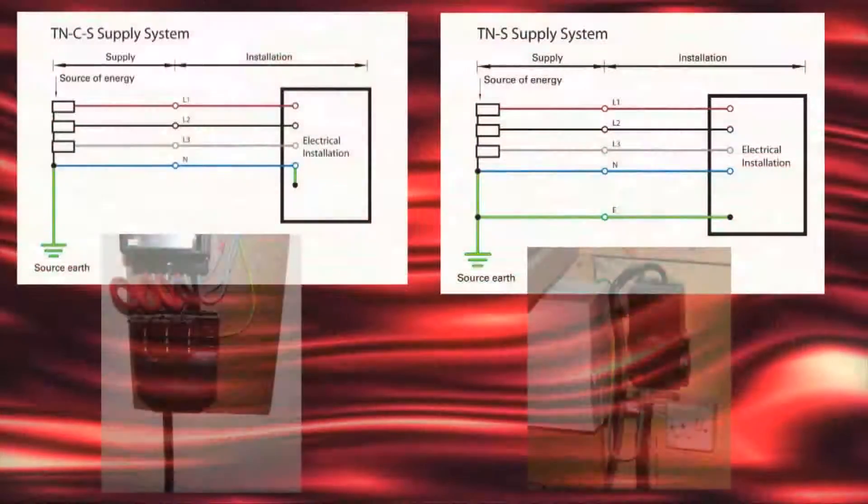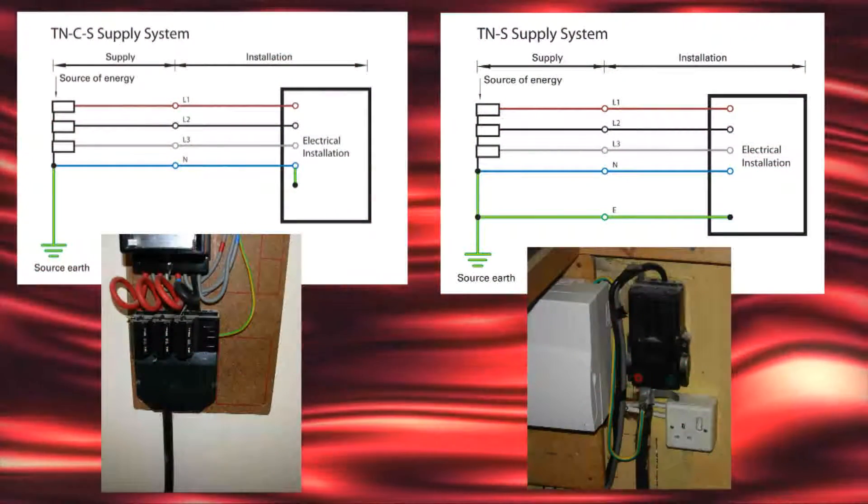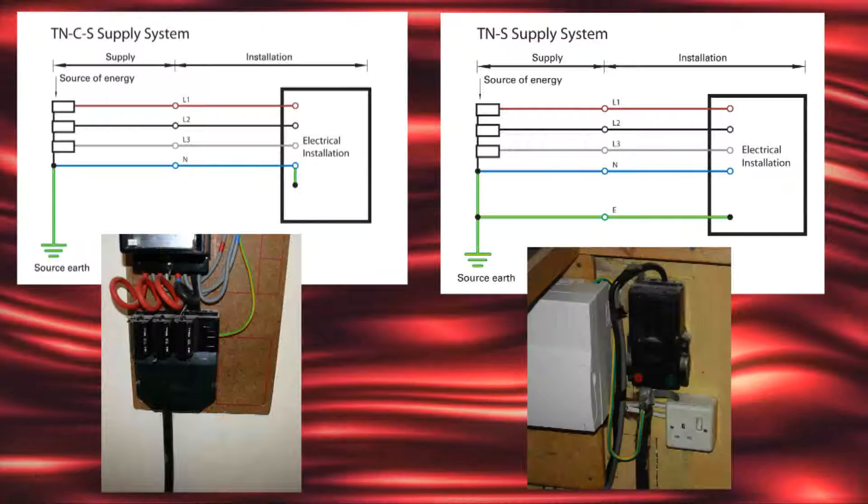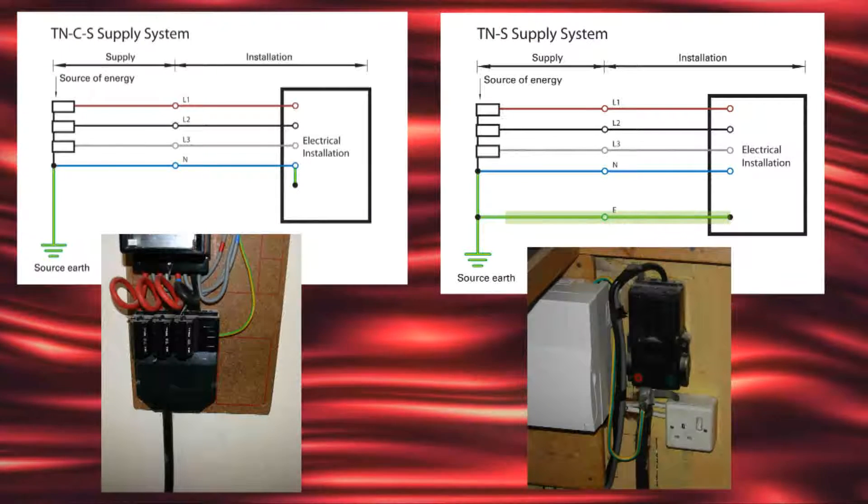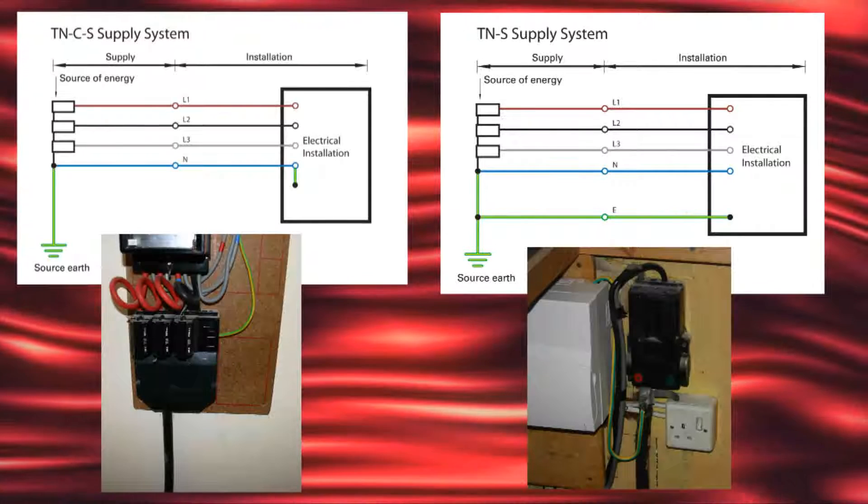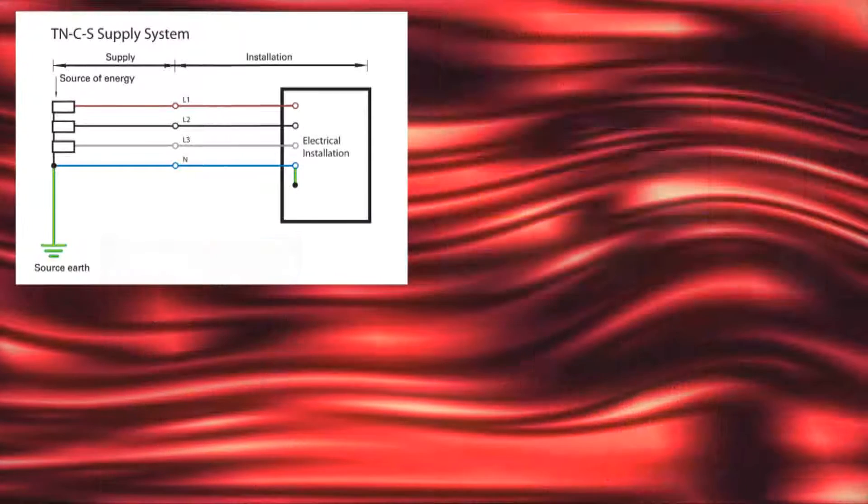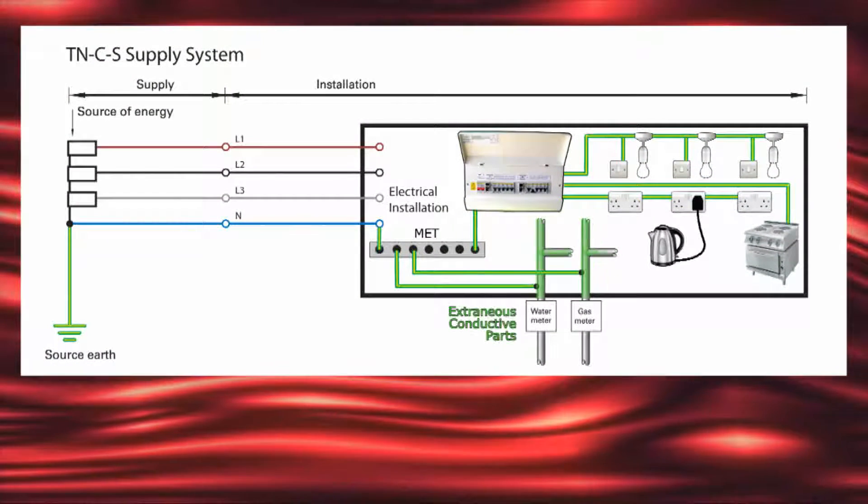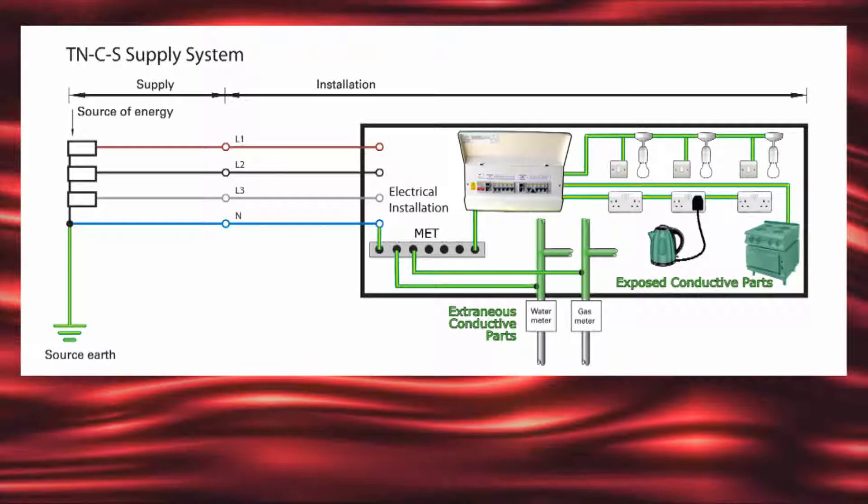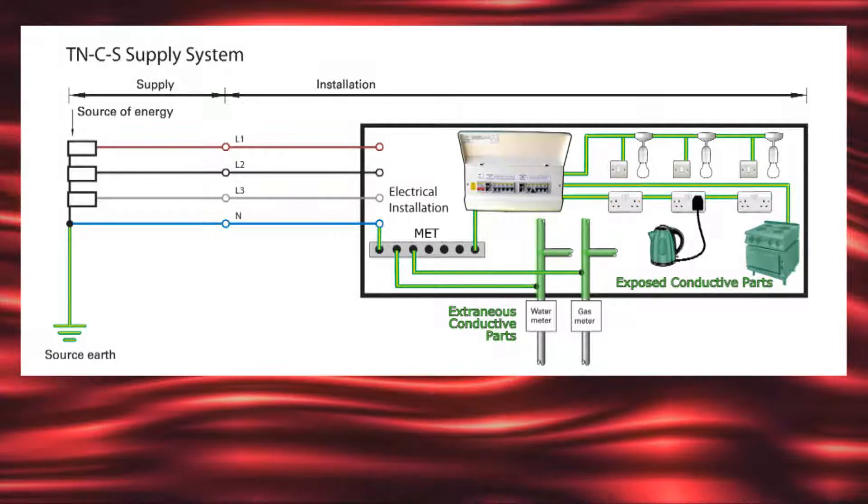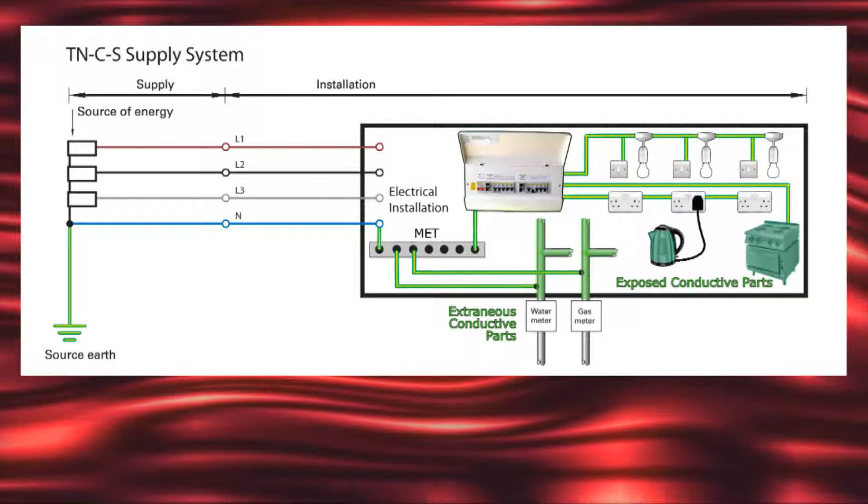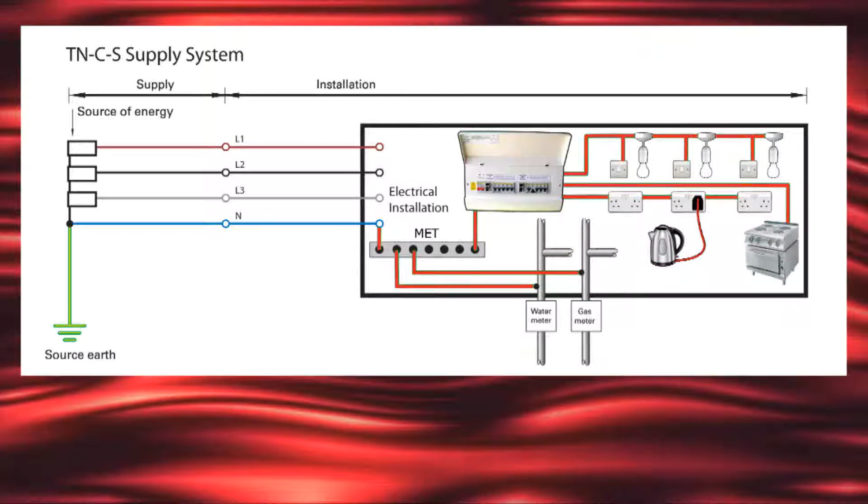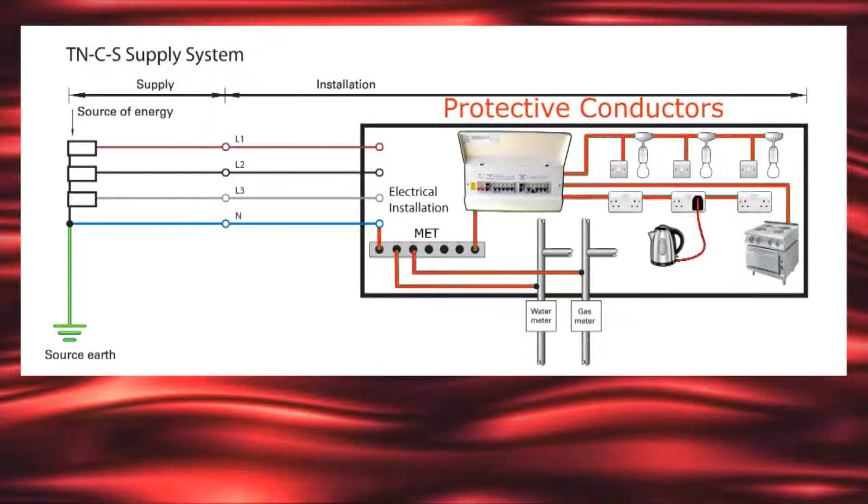TN systems often provide a low impedance path for earth fault currents by adopting either the existing supply neutral conductor in a TN-C-S system, or a separate protective conductor such as the metallic sheath of an armoured cable in a TN-S system. For this to work as a complete protective system, all extraneous and exposed conductive parts within the installation must be connected to the external earthing arrangement. They will then be regarded as being at the same electrical potential as earth. The conductors within the installation providing this connection to earth are known collectively as protective conductors.